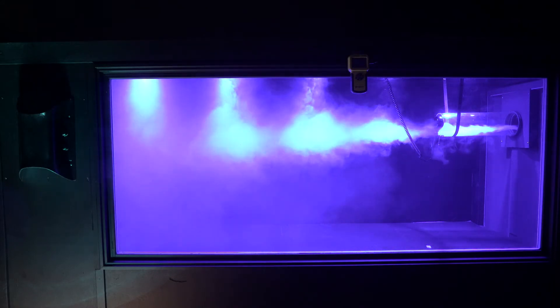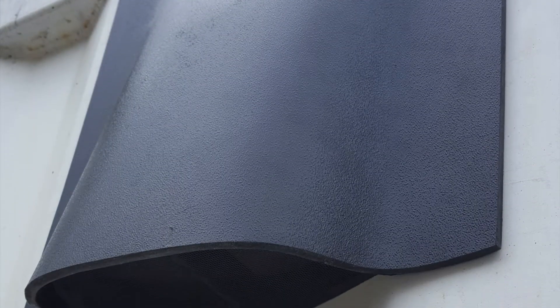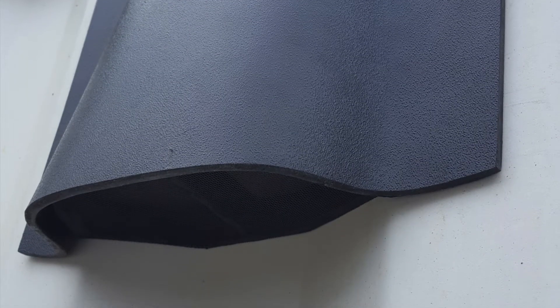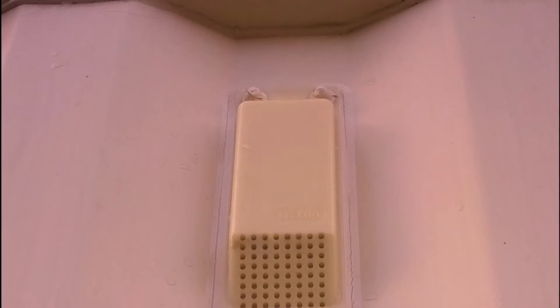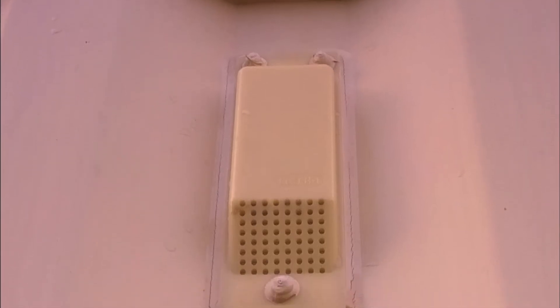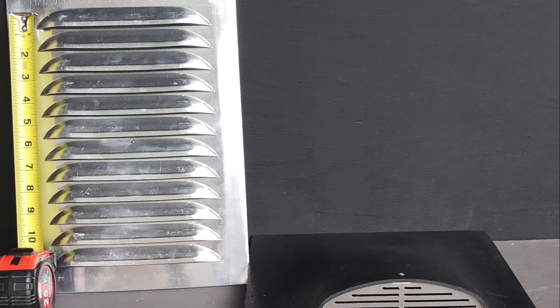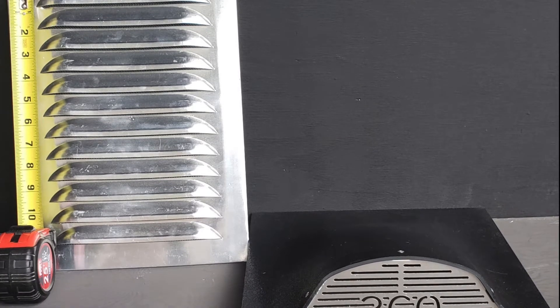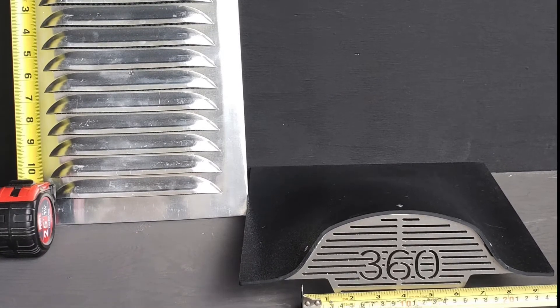These readings are taken from the air entering the enclosure. Passive vents do not have airflow specifications, as they do not force airflow. They can only be used for air intakes unless a fan is installed behind them. On their own, cross-flow ventilation is not possible.